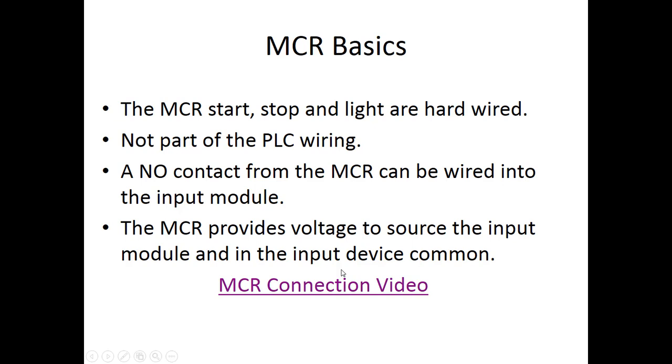Okay, so the MCR basics. There is an MCR connection in the lab. I just wanted to remind you how to do that. We're going to use the normally open contact of the MCR to be wired into the input module. We're going over this a little bit so that when we get to safety relays, you'll have some knowledge of how a safety relay might be used to trigger the PLC that the MCR is actually on. The MCR provides the voltage to source the input module and input, and I show those connections here if you want to take a look at that.